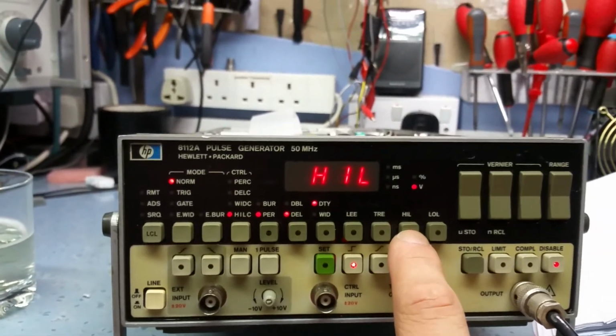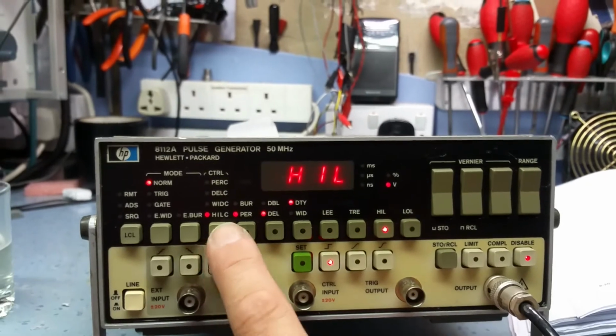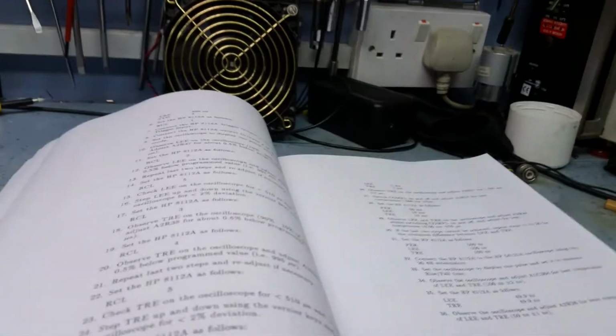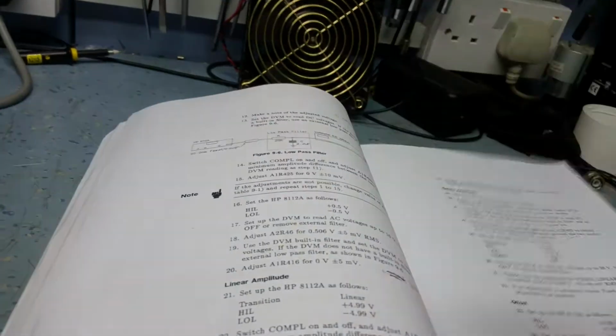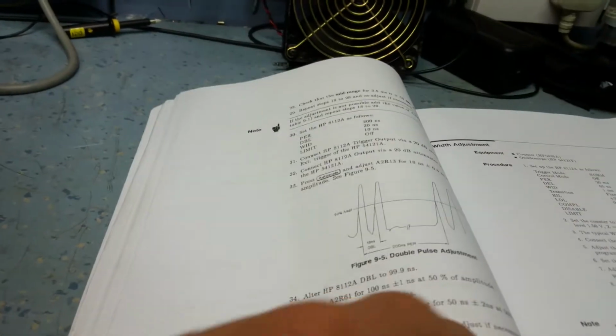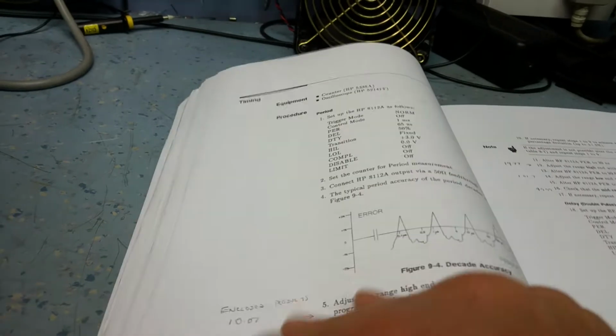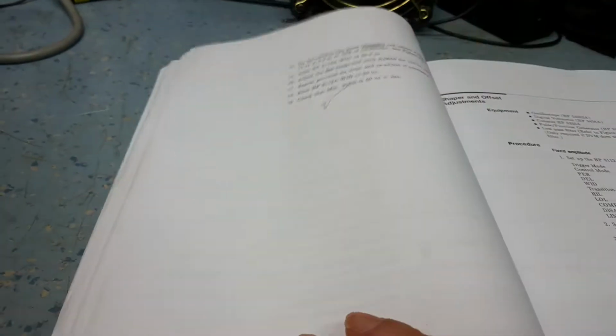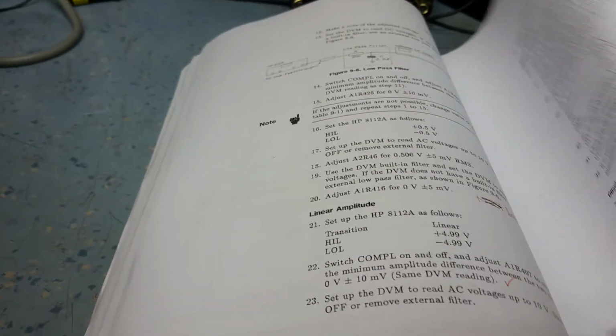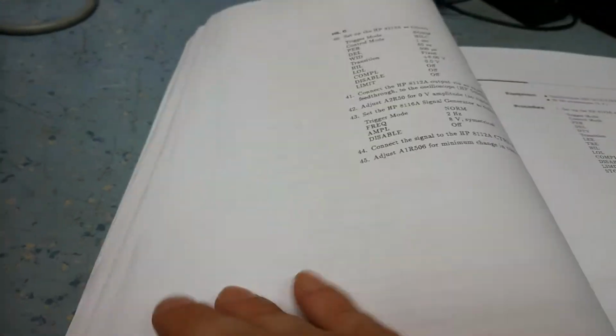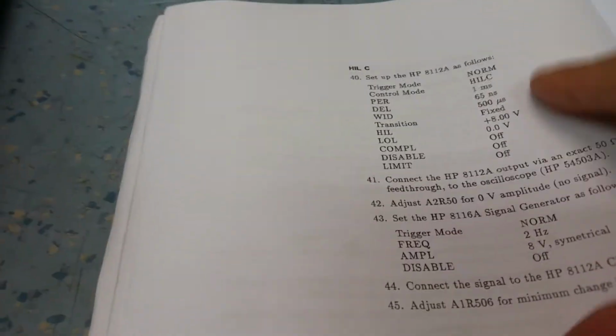So this is producing its maximum output. But that requires a calibration to be correct in the calibration procedure. And let me just see if I can show you where that is. I've gone past it actually. It's towards the end. And funny enough, I flicked through the calibration previously and I thought, well, it all looks okay. No, there's no problem there. So I thought, well, it's obviously a hardware fault. Here we go. HIL C.